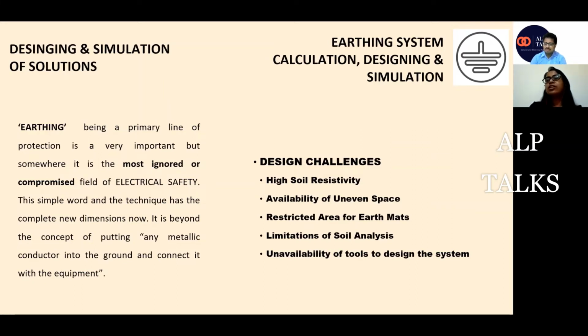But for the areas with higher soil resistivities, like more than 50 ohm meters, 100 ohm meters, it is very difficult to achieve. Also, it is very difficult to maintain the earthing pit for a longer life, because earthing is the only thing which is carrying the fault current, in any fault situation, into the ground. It is very important that it will remain there for a longer run.